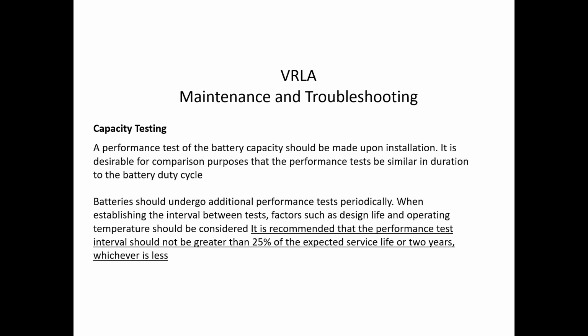But load testing is an expensive process. Depending on the quality of the people doing the work, it jeopardizes your system, your load. You really have to know what you're doing. My personal recommendation on valve-regulated battery is probably after 5 years of installation. Do an acceptance test if you can when installed, but then after 5 years in service, I would base it on conductance readings, and then maybe you go to every 2 to 3 year period of load testing. No one can afford to do every 2 years. But again, it's a recommendation.